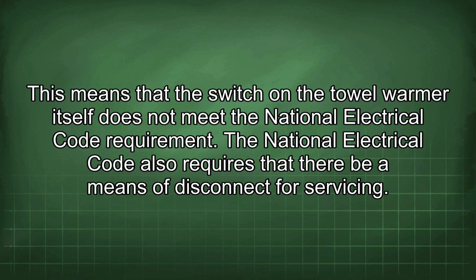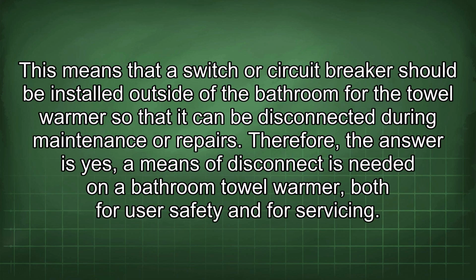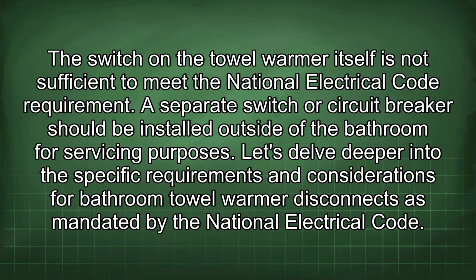The National Electrical Code also requires that there be a means of disconnect for servicing. This means that a switch or circuit breaker should be installed outside of the bathroom for the towel warmer so that it can be disconnected during maintenance or repairs. Therefore, the answer is yes, a means of disconnect is needed on a bathroom towel warmer, both for user safety and for servicing. The switch on the towel warmer itself is not sufficient to meet the National Electrical Code requirement. A separate switch or circuit breaker should be installed outside of the bathroom for servicing purposes.